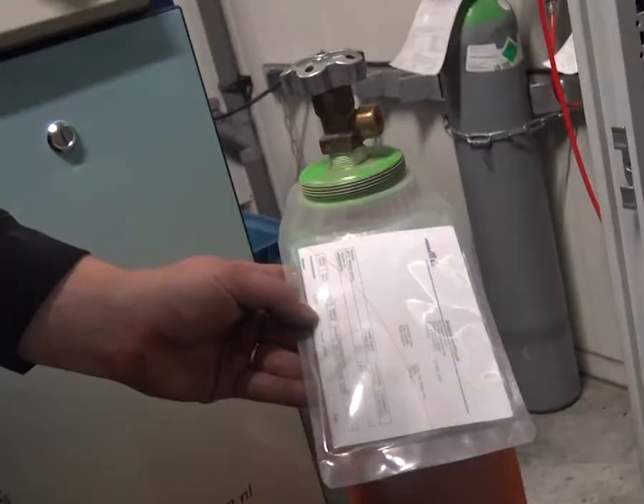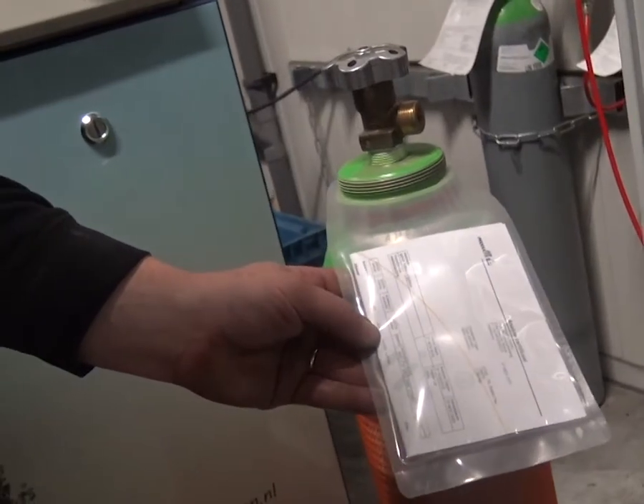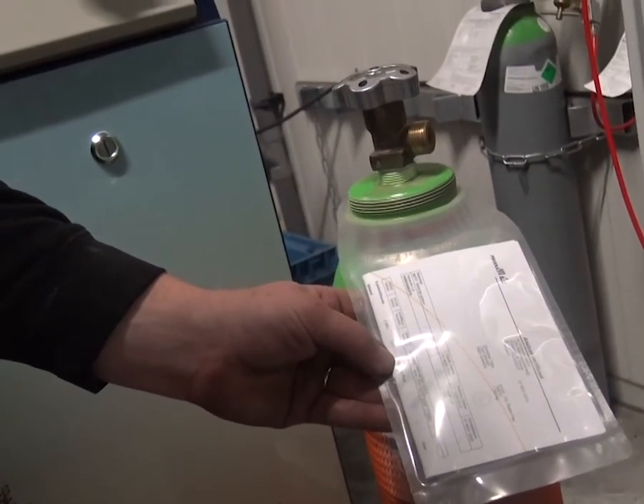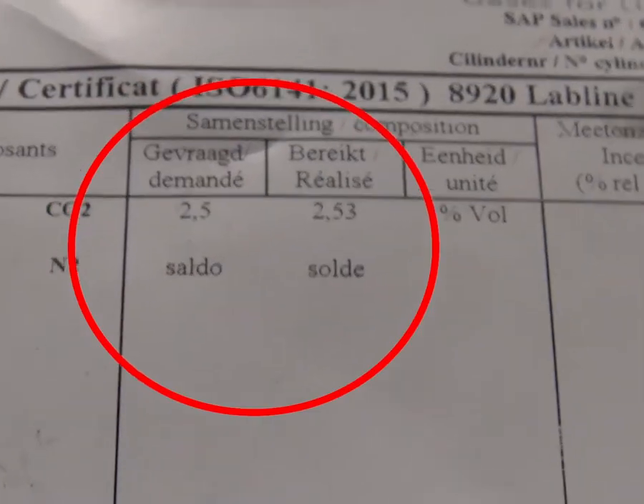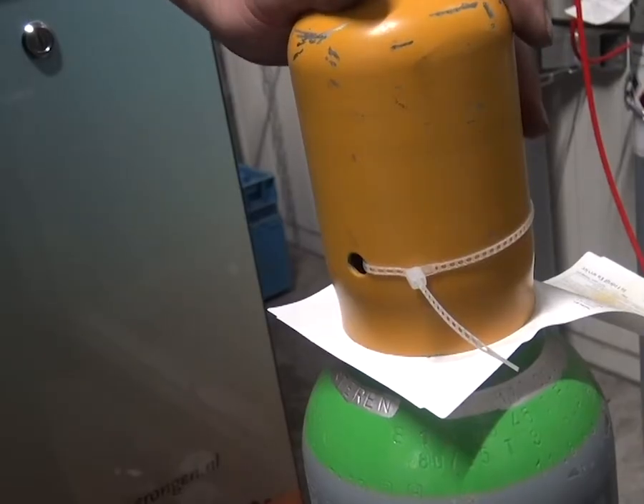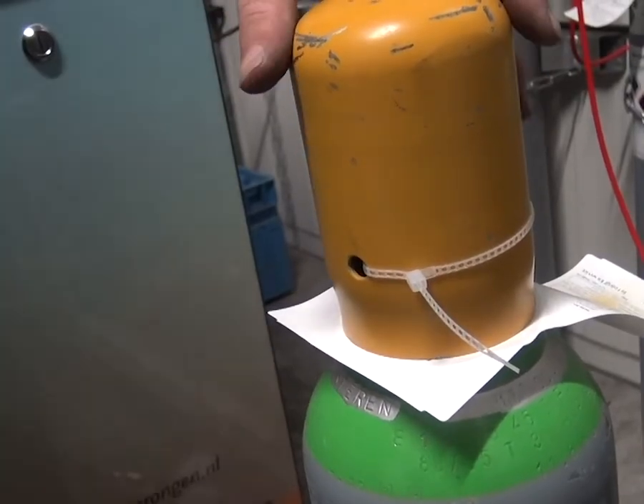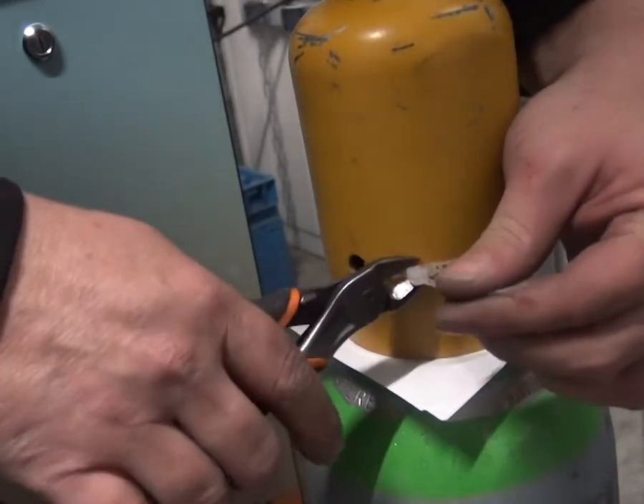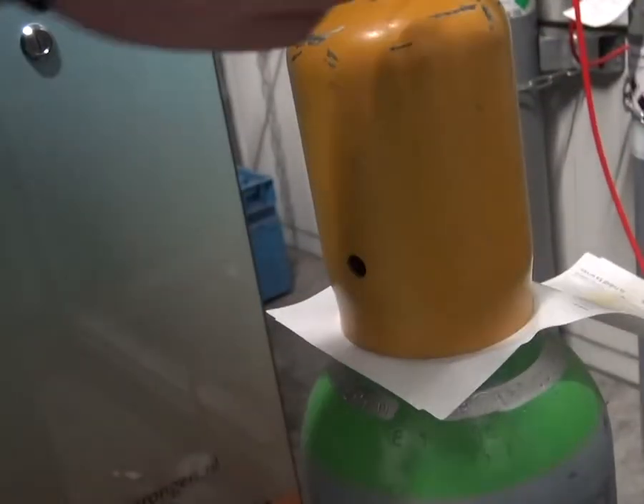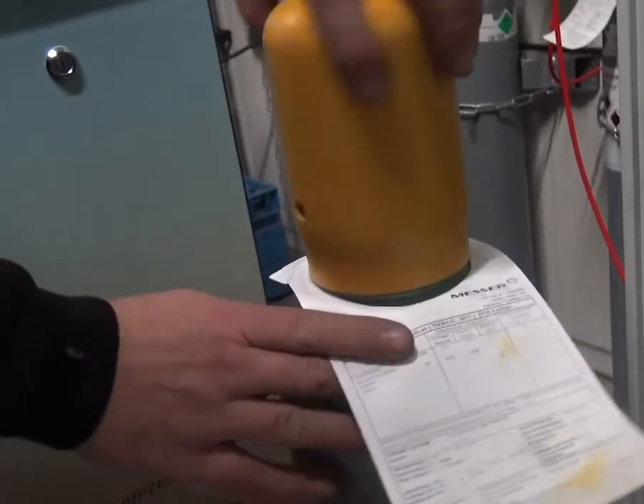Check the certificate on the calibration gas bottle for what the old values are, and check if the new bottle contains the same certificate and values as the old one. Check if the new bottle is sealed. In most cases this has been done with a cable tie. Cut the cable tie and turn the safety cylinder off the new bottle.